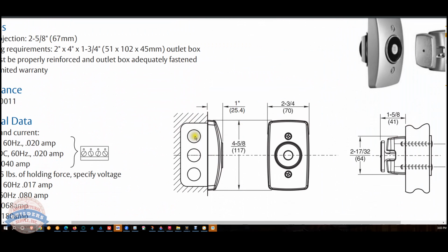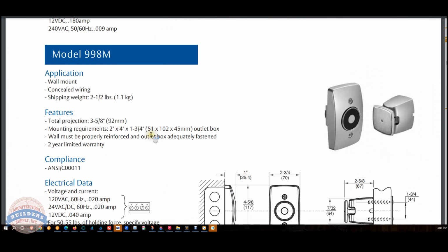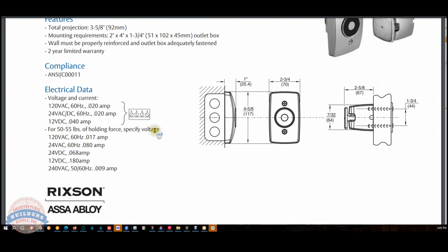Now the question is, will the client be able to install this flush? The wiring needs to be inside the wall. I doubt that's going to be the case. So based on the 997, will they be able to get the power to the unit by some other means or from some other path? Because surface mounting it is going to lead us to a much greater dimension required, such as the 996M, and that's going to be 4⅛. So let's first draw something at 2⅝ for the 997, and let's see what happens.